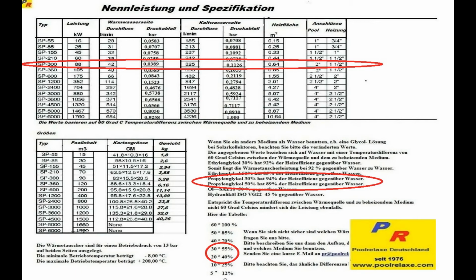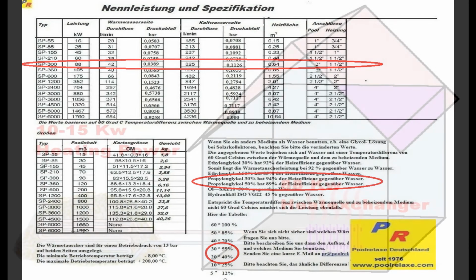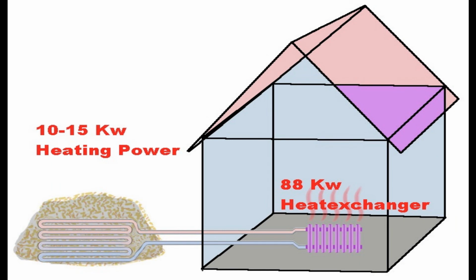We will be using a mixture of water and frost protection as a medium. That reduces another 10%, dropping the heat exchanger to about 31.5 kilowatts. Throw in some insulation loss of 5% and we have around 30 kilowatts effective real heat transfer. Compost heating should not be run permanently, but in cycles to give the medium time to warm up again. Compensating for these cycle times, a 30 kilowatt heat exchanger for 10 kilowatt heating should be a reasonable rate.